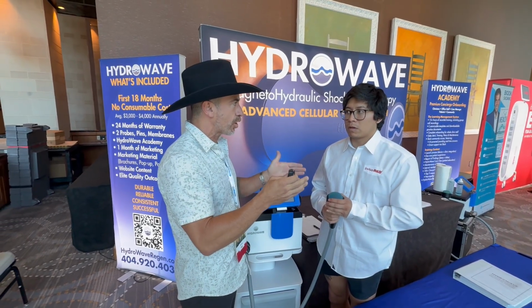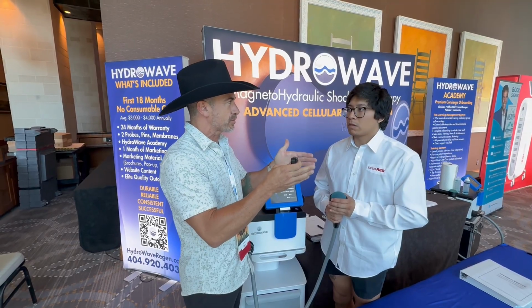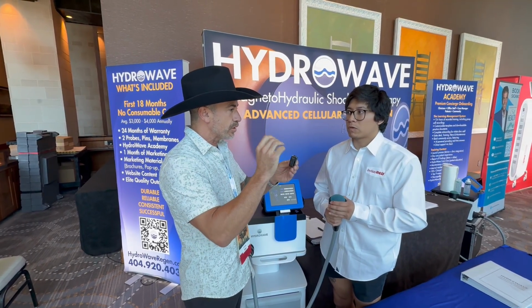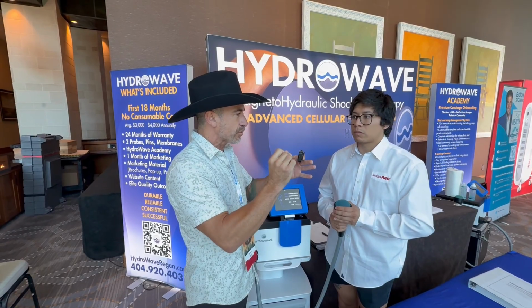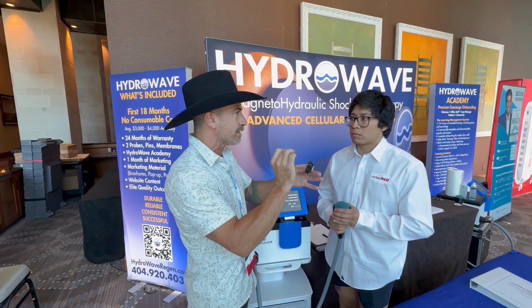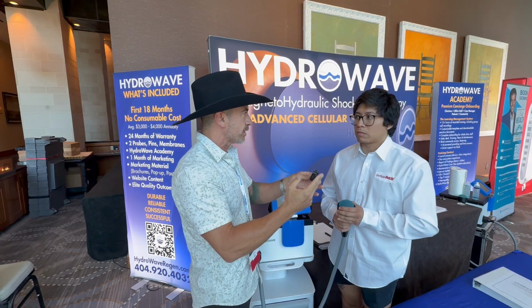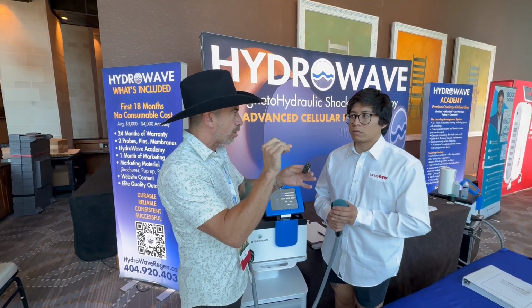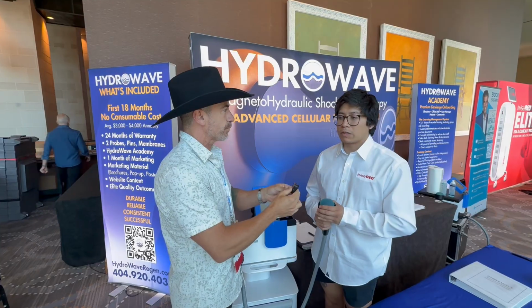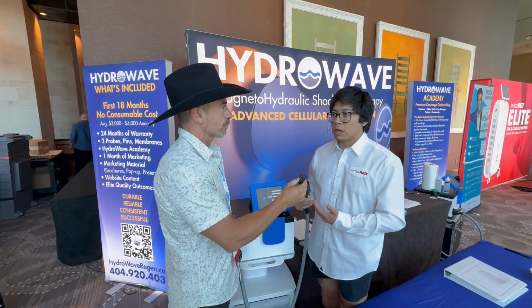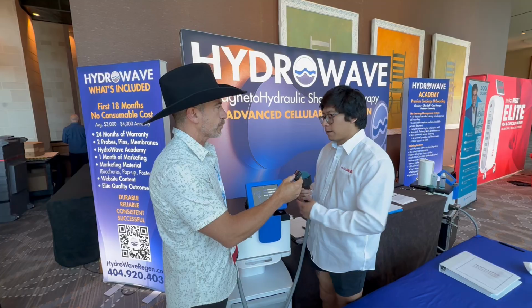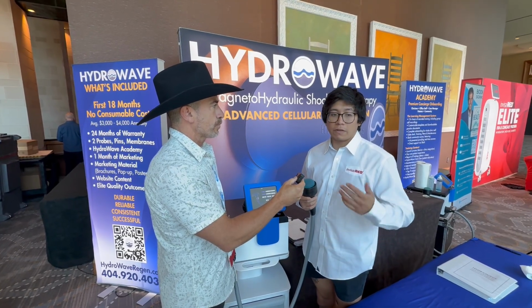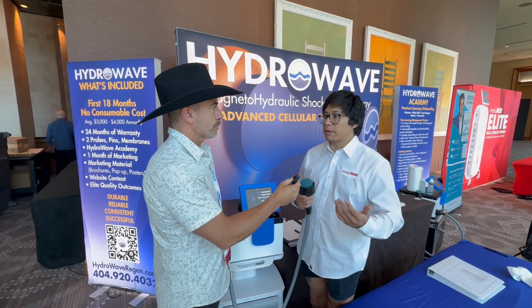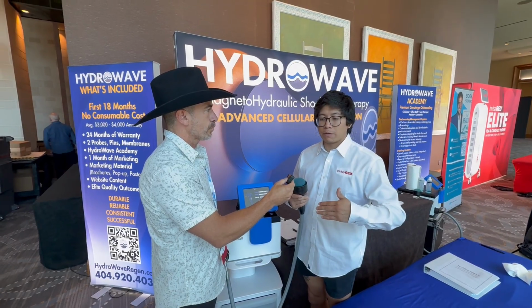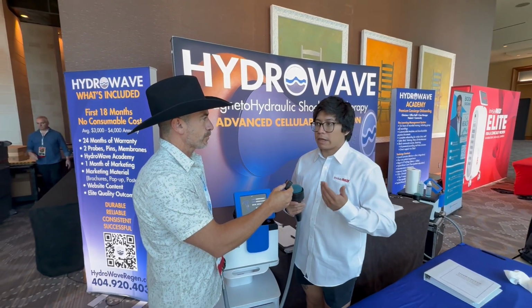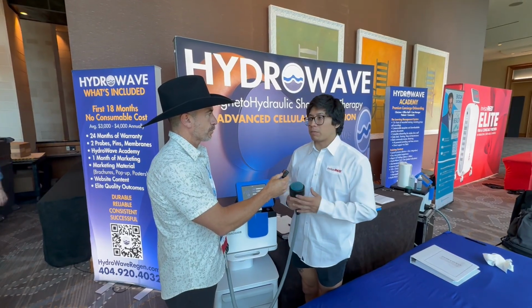So you can start broader to see what is going on, so it saves time there. But then once you find the area, you can increase the water pressure, so you start to pinpoint exactly where the inflammation or the injury is. And then you can really focus on the specific targeted areas. Yes, which is going to lead to the patient getting better results. You're not wasting shots on your device or time out of their calendar or schedule to get more treatment. So the faster you find the injury location for the patient, the better we can start treating and get the actual energy dosage that it needs to get the therapeutic benefits from it.